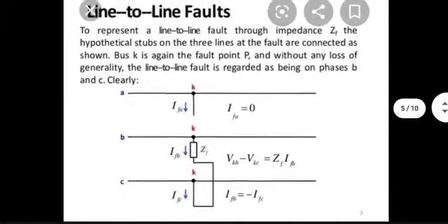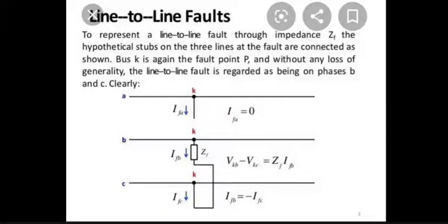The other possibility is line to ground faults, LG faults, where between one line and the ground, you may have undesired impedance, short circuit almost. So this is the LL fault situation that we are showing. And some possibilities are being shown, not all possibilities. Between line B and line C, an impedance has been created somehow, which is not very large. So you have a short circuit case, almost a short circuit case.